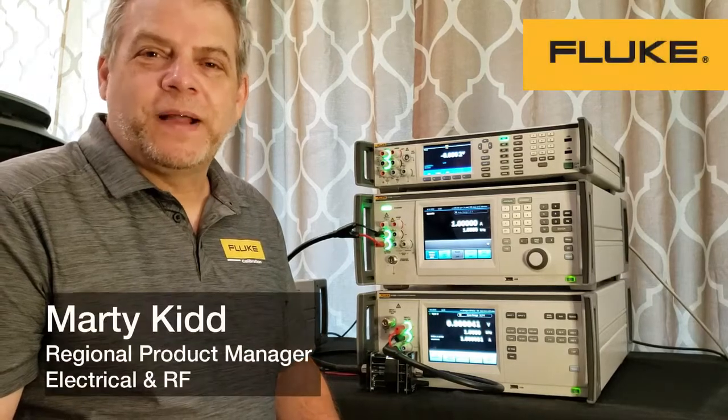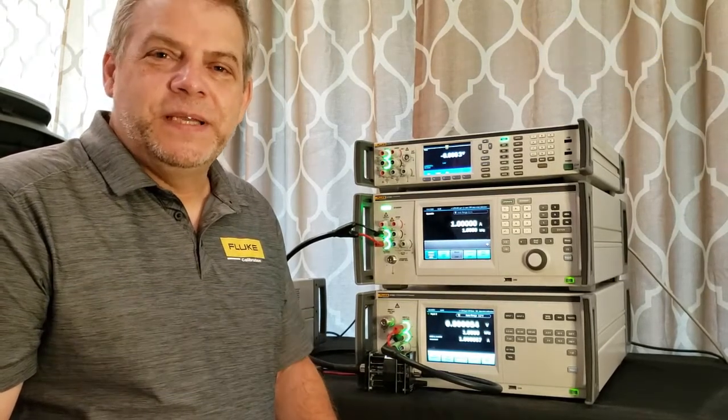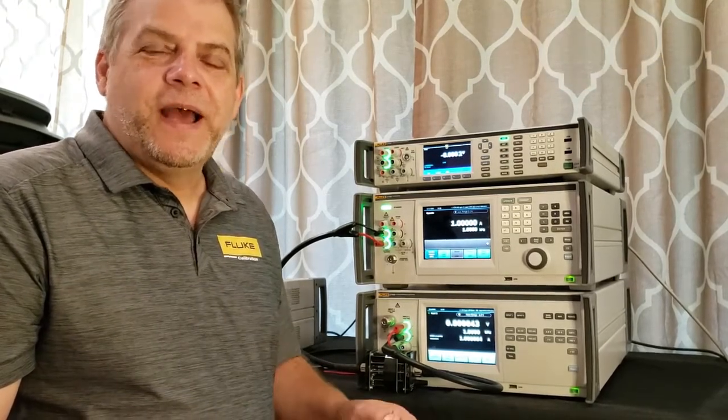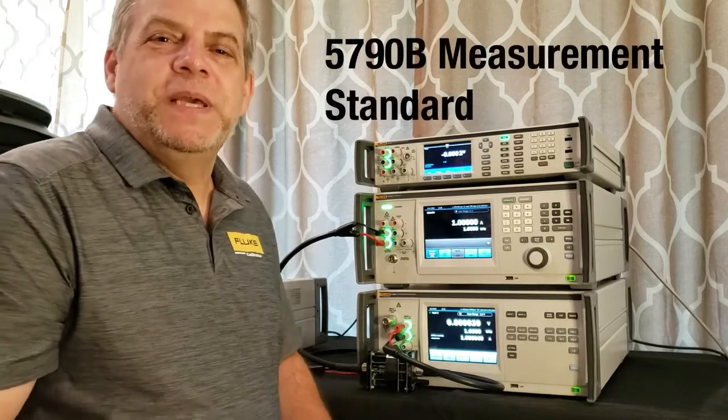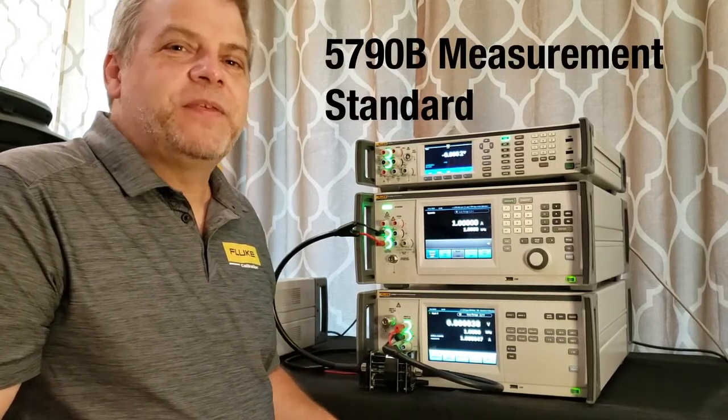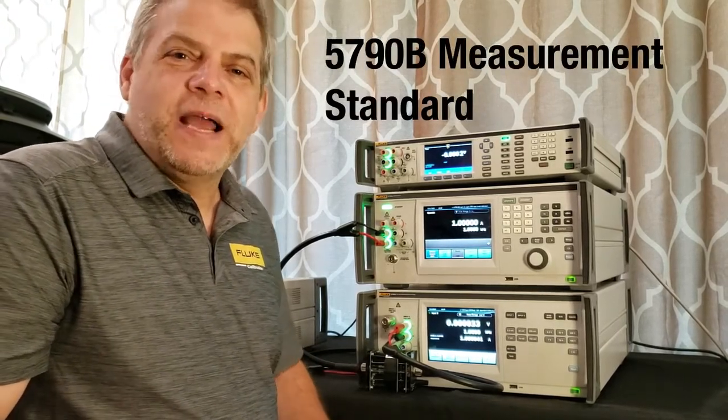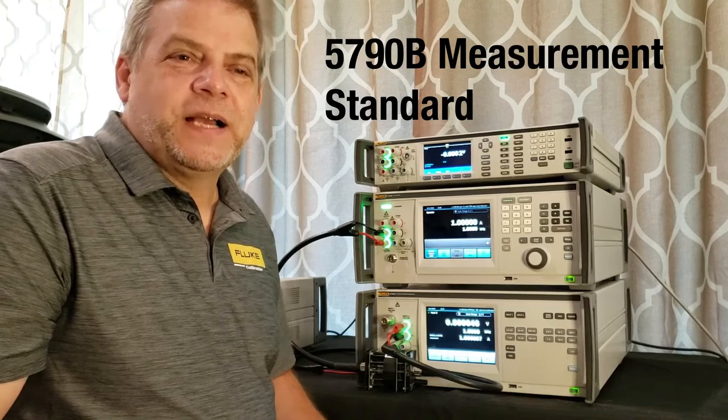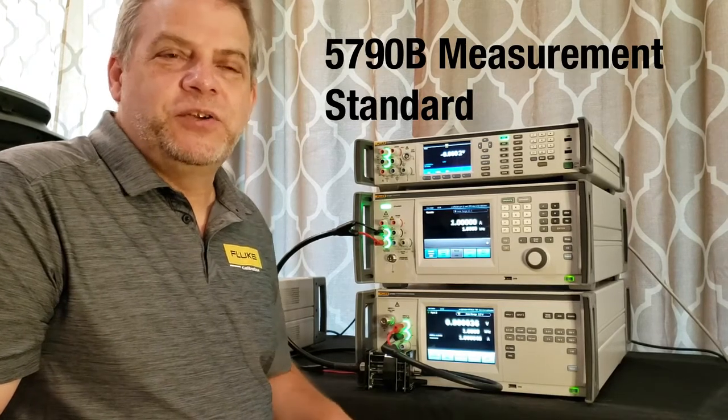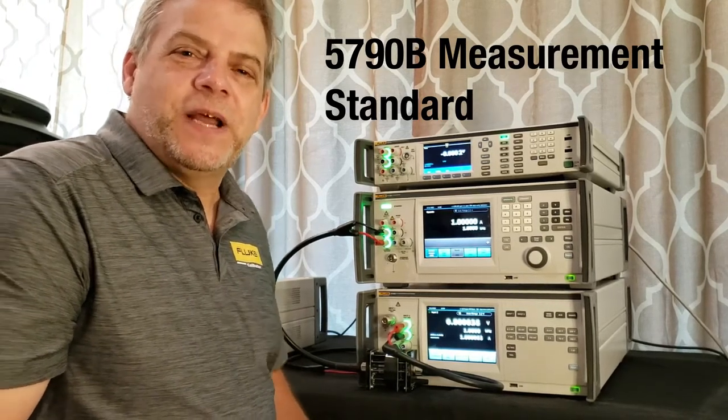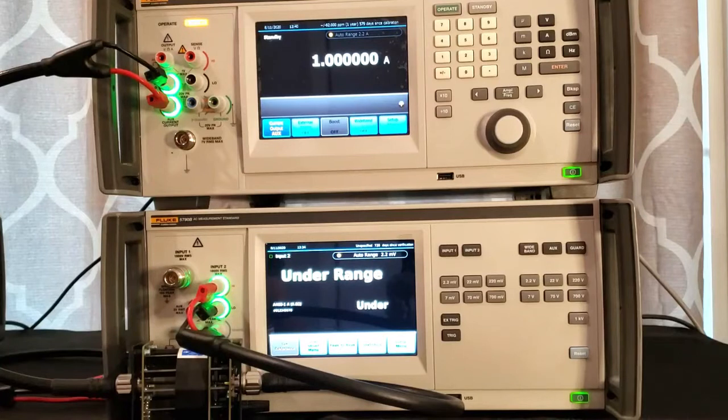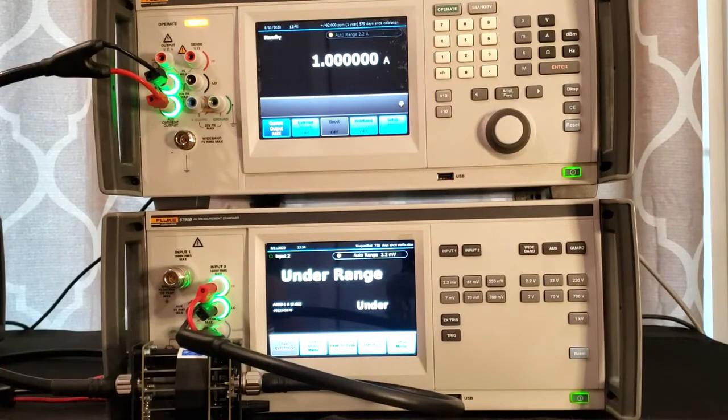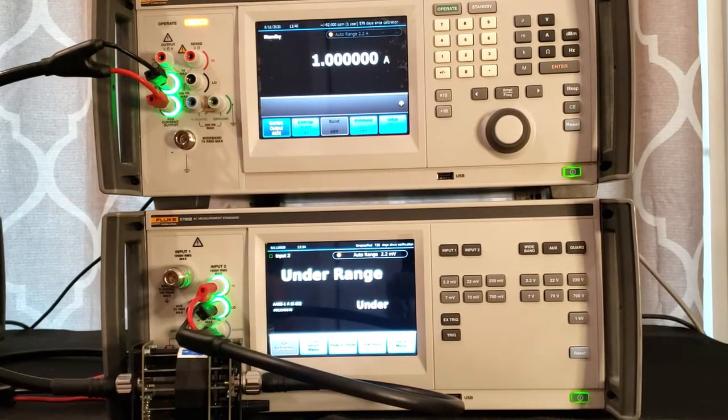My name is Marty Kidd with Fluke Calibration. Today I'm going to be demonstrating how to use an A40B current shunt with a 5790B as a detector to use the corrections in the 5790B to give you the actual output readings from the A40B.